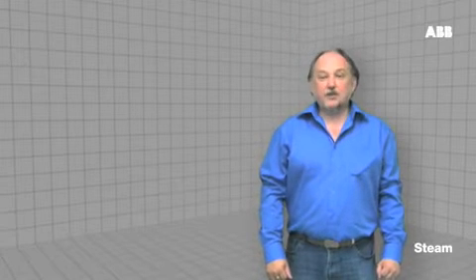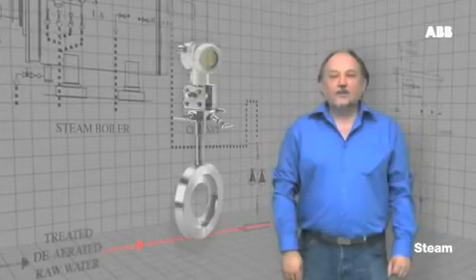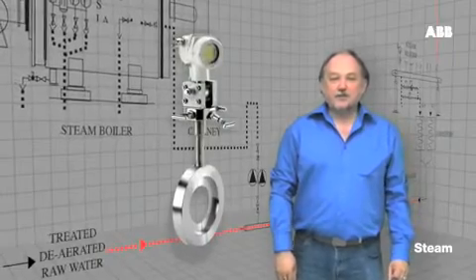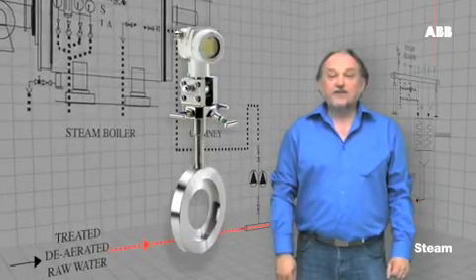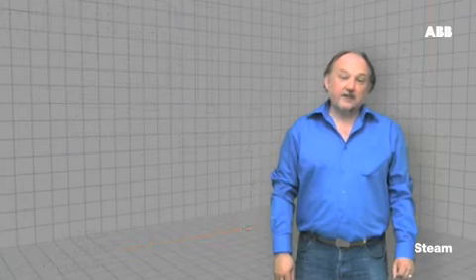Because the density and quality of steam varies continuously, measurement in actual volumetric units can be inaccurate. The key to accurate, consistent measurement of steam system efficiency is to use mass flow measurement of steam output and distribution to identify low efficiency boiler operation and plant areas or machines with poor leakage performance or reduced efficiencies.